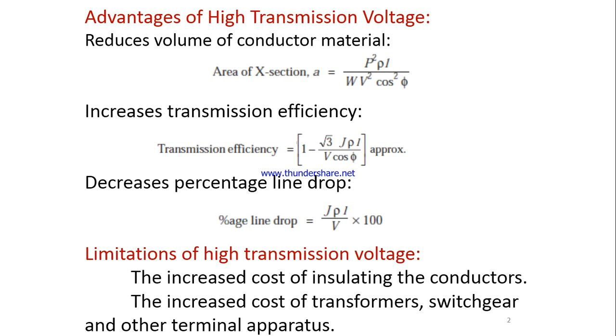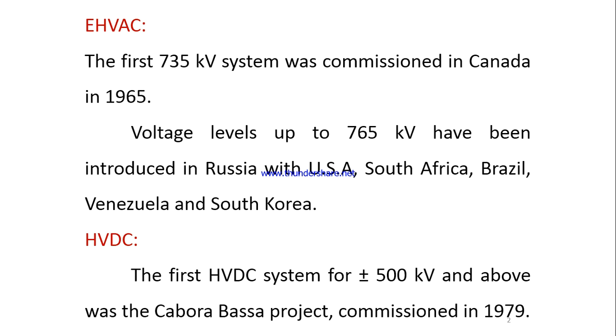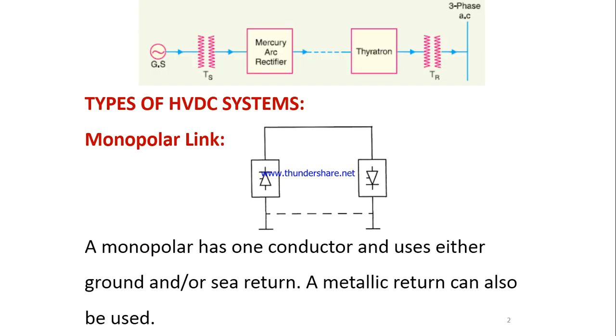So, let us consider high voltage transmission. It reduces the volume of conductor material, increases the transmission efficiency, and decreases the percentage voltage drop. But the limitation is the cost. It will be a costly one. While considering EHVAC, the first one is a 735 kV system which was commissioned in Canada in 1965. Voltage levels up to 765 kV have been introduced in Russia, with USA, South Africa, Brazil, Venezuela, and South Korea. But while considering HVDC, the first HVDC system for plus or minus 500 kV and above was the Cabora Bassa project, which was commissioned in 1979.